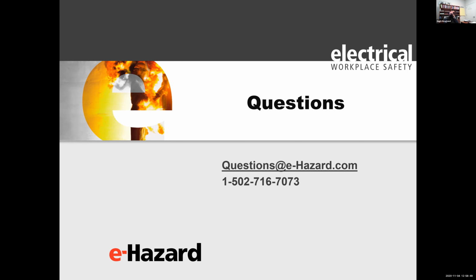And so you may see that somebody just puts an arc rating on it, but if it has an arc rating and it meets 1506 or 61482-2, then it is flame resistant. And by definition, at least we should have a vertical flame test to do the arc test, because if it doesn't pass the vertical flame test, it typically will burn off the panel in an arc test.